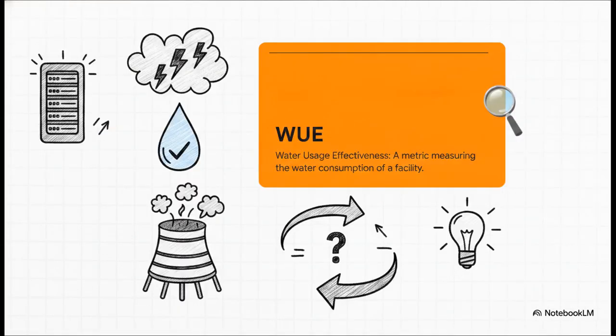But wait, then we have WUE, or Water Usage Effectiveness, which measures the facility's water consumption. And herein lies the ultimate dilemma. An air-cooled system might have a worse PUE because it burns more electricity, but it boasts an excellent WUE because it conserves water. Meanwhile, a water-cooled system saves electricity but has to evaporate massive amounts of water to pull it off. So what do you do? Save water but burn electricity, or save electricity but consume vast amounts of water? Facility owners are forced to constantly balance the two.